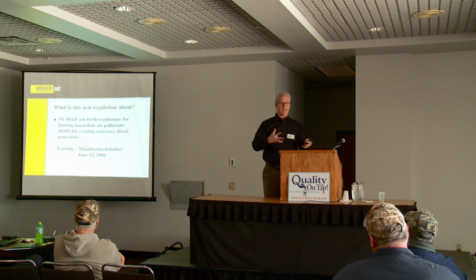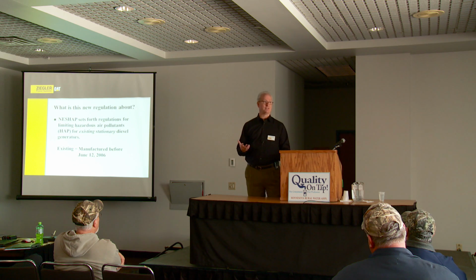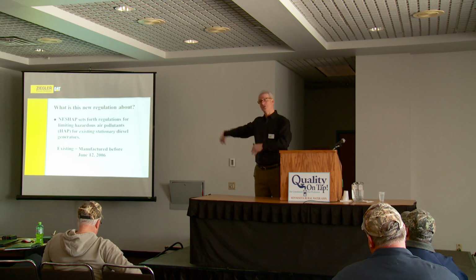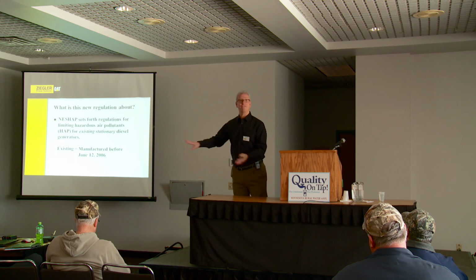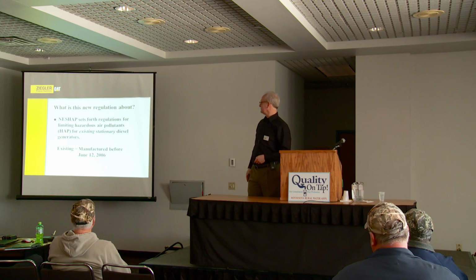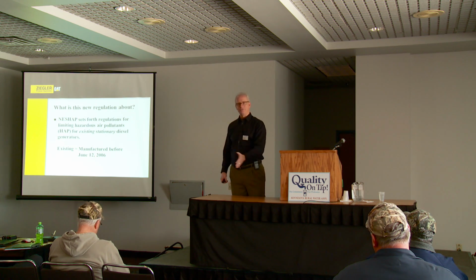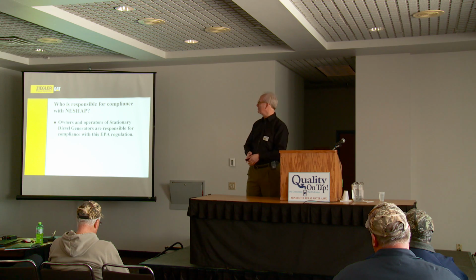So if you had in front of you, I know you don't, all the diesel engines you've got in your cities, and you knew when each was manufactured, it's like, okay, if it was manufactured after June 12, 2006, now you can really go to sleep, because the stuff I'm going to talk about from now on doesn't apply to you. The NESHAP rule says the only thing you have to do is follow the new source performance standard, under which your engine would have been purchased. So, does this apply to me? June 12, 2006. If that engine's got a date on it after that, then you don't have to worry about NESHAP. That's the really simple version of the story.